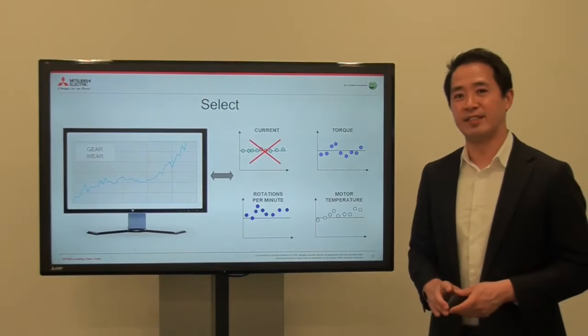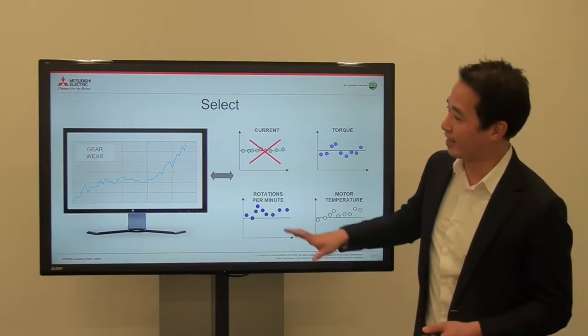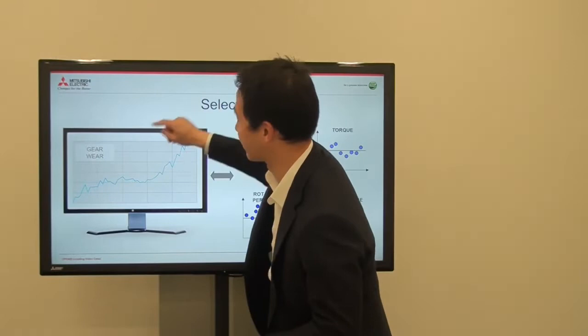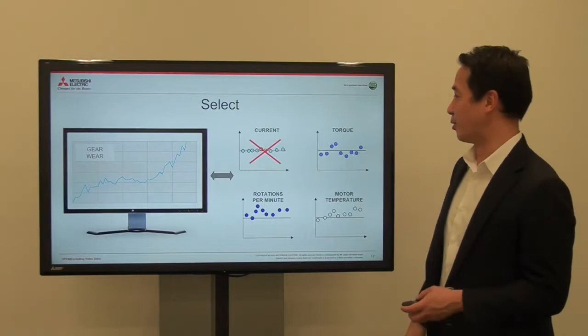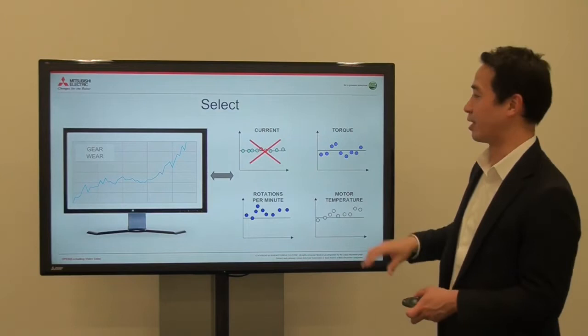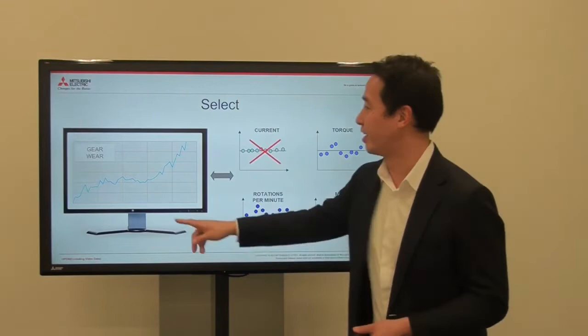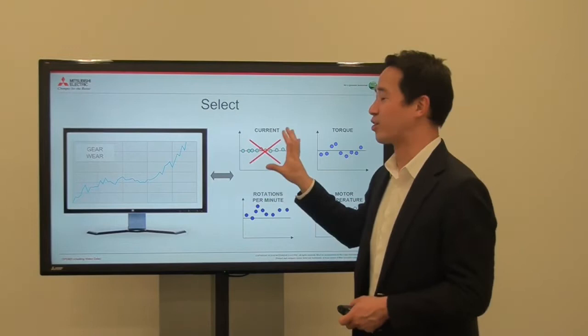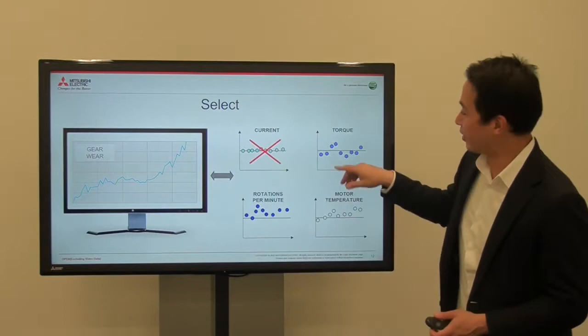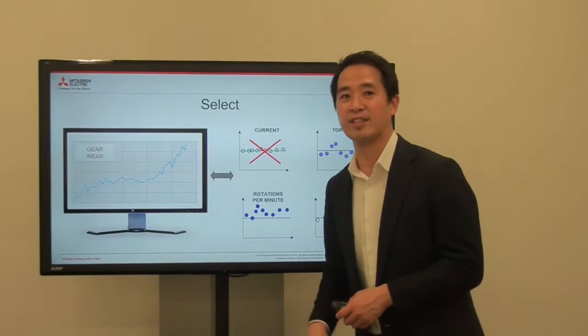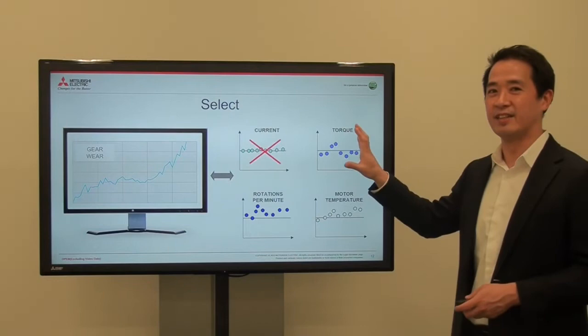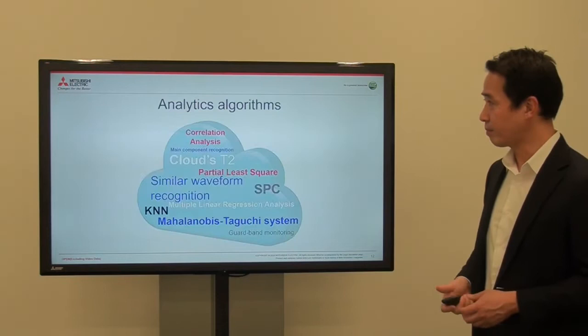The next phase is selecting the data that is relevant to the gear wear. The gear wear will go up — it's wearing down every day — so it shows an upward trend on the chart. If you look at the other data, for instance around the motor — you see the current, the torque, the rotations per minute, and the motor temperature. If the current is a straight line while the gear wear is moving, that means the current data probably has nothing to do with the gear wear, so you throw it out. But if other data is moving around, it might have relevance to the gear wear, so keep it and use that data to analyze. Selecting the data you need, and not using everything, is very important.